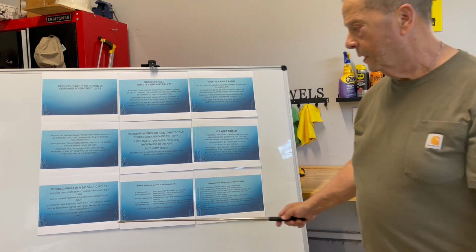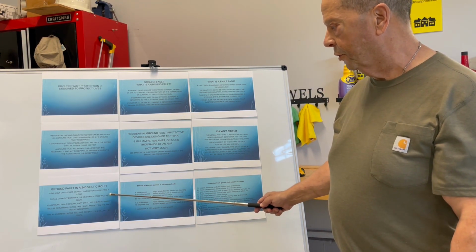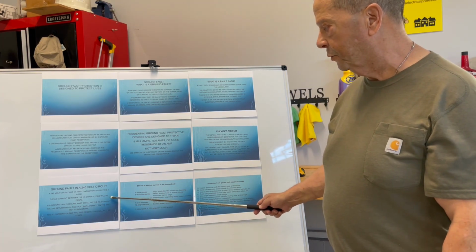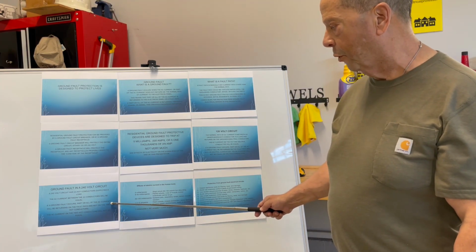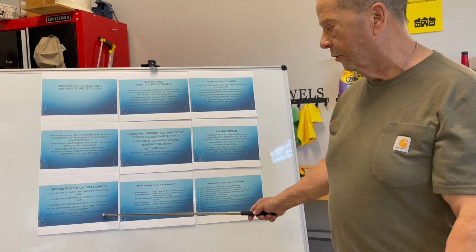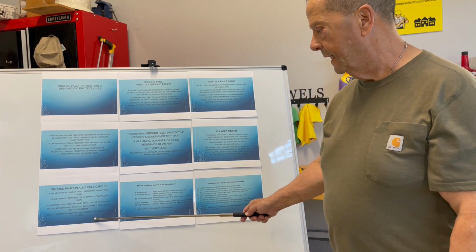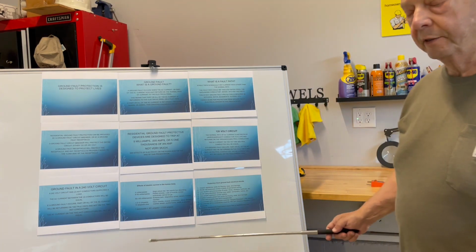Ground fault in a 240 volt circuit. A 240 volt circuit has two hot conductors supplying a load. The AC current between the two conductors will be equal. If a ground fault occurs, part or all of the AC current will be returning on the fault path and not on the two hot conductors. The AC current on the two hot conductors will not be equal and your ground fault protection will trip.